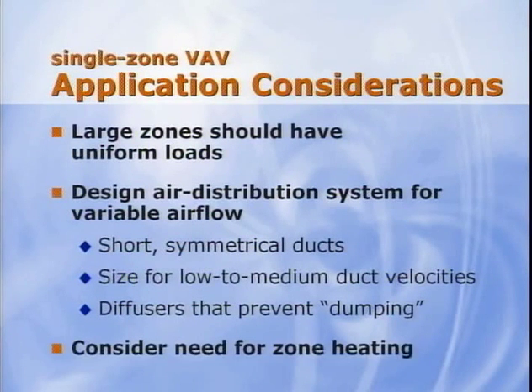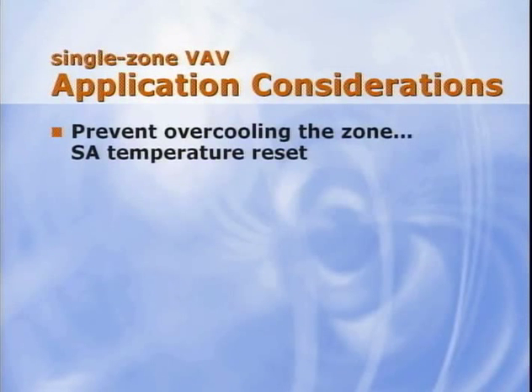Third, consider the need for heating in the zone. Typically, a source of heat is provided in the rooftop unit. When the zone needs heating, the rooftop unit stages heating capacity to maintain space temperature. In packaged DX rooftop units, the supply fan can typically turn down to about 30% of the design airflow. In a zone with a widely varying load, the sensible cooling load may become small enough that the required supply airflow is less than the minimum airflow that can be delivered by the supply fan. Under this condition, the zone will be at risk of being overcooled. One way to prevent overcooling is to reset the supply air temperature upward at low load conditions. This avoids overcooling the zone, but the amount of reset must not cause excess humidity levels in the zone.